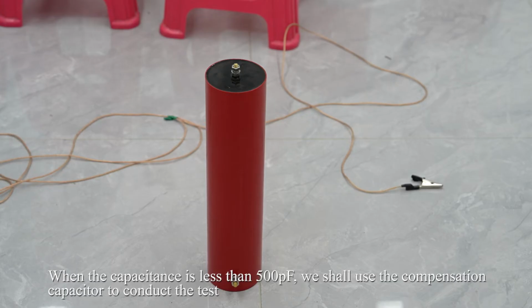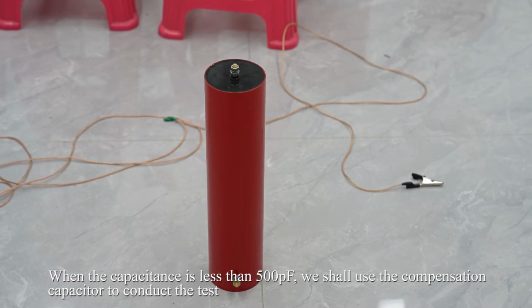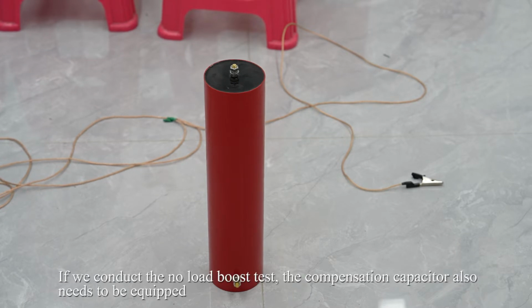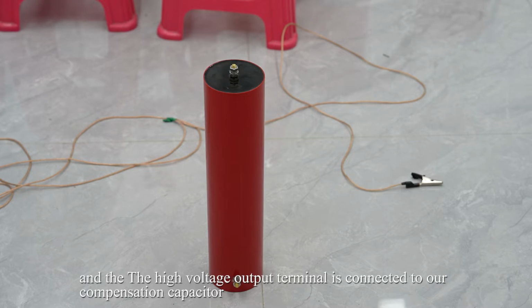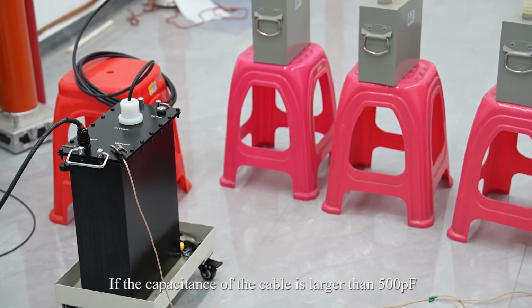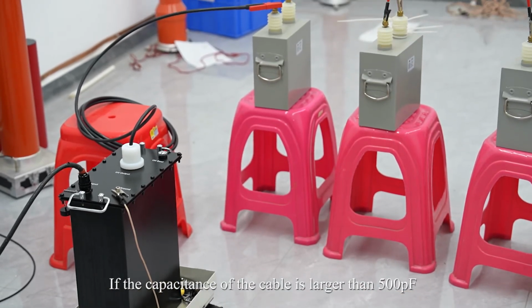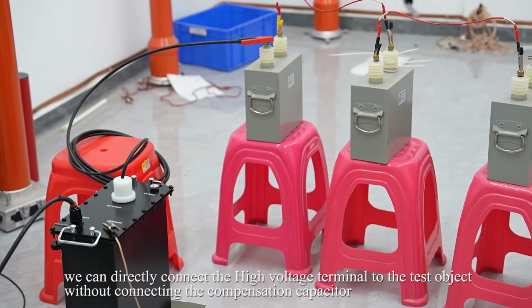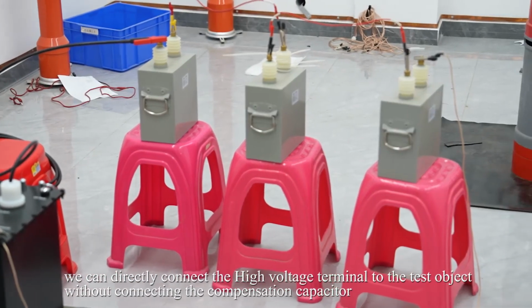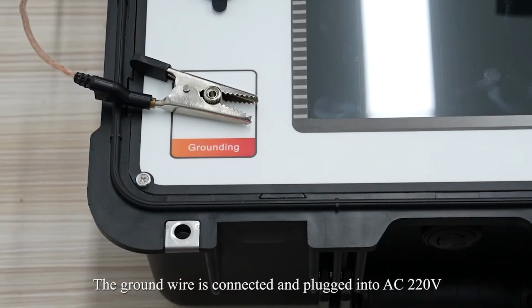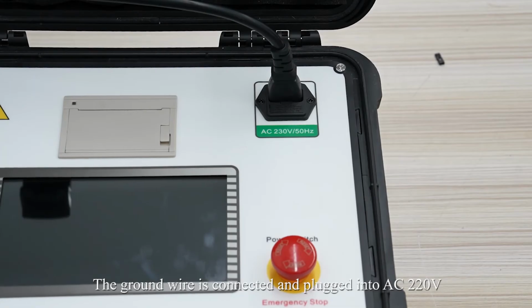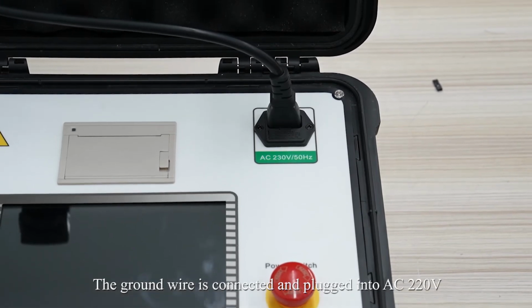When the capacitance is less than 500 picofarads, we shall use the compensation capacitor to conduct the test. If we conduct the no-load boost test, the compensation capacitor also needs to be equipped, and the high-voltage output terminal is connected to our compensation capacitor. If the capacitance of the cable is larger than 500 picofarads, we shall directly connect the high-voltage terminal to the test object without connecting the compensation capacitor. The ground wire is connected and plugged into AC 220V.